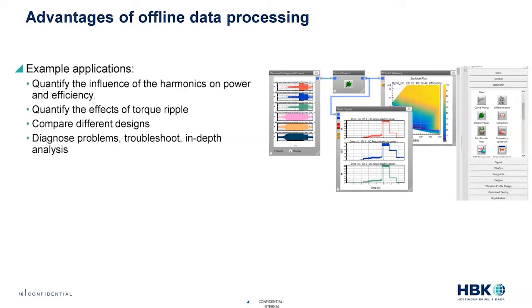What we typically use post-processing software for is to quantify, for instance, the influence of harmonics on power and efficiency. As you know, the currents and voltage coming from the inverter are far from nice sinusoids. If you do the power spectrum of these signals, you'll see loads of harmonics, and if you look at the signals they look very noisy because of all those harmonics on top, which has an influence on the power and efficiency of the inverter.